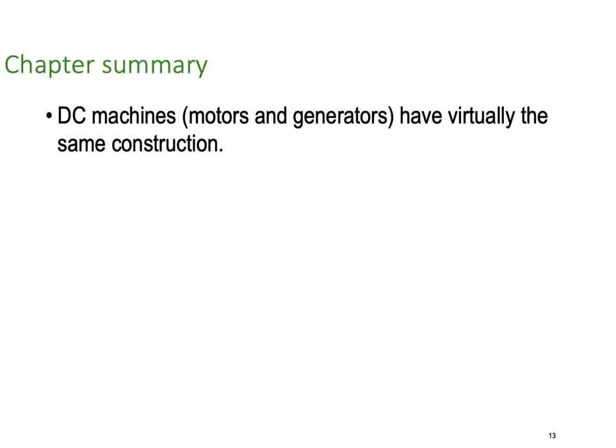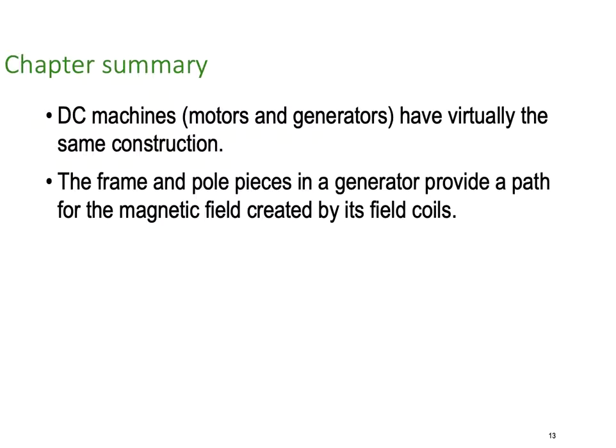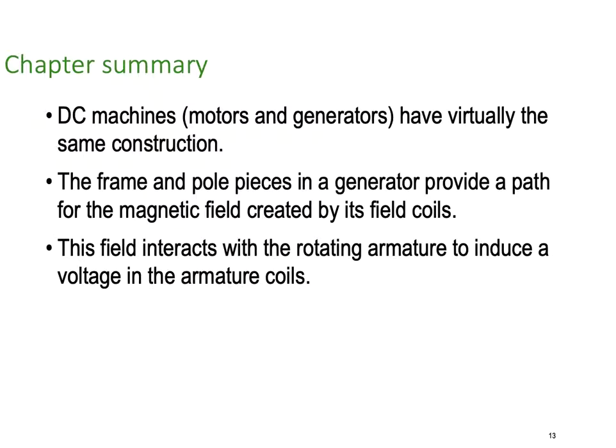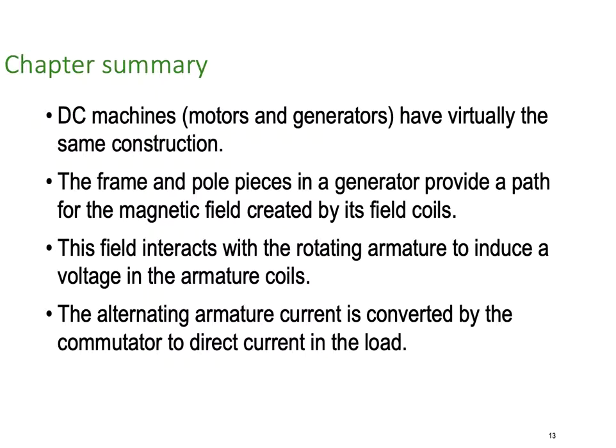Let's have a summary of the lesson. DC machines - motors or generators - have virtually the same construction. A generator can be a motor and a motor can be a generator in the DC world. The frame and pole pieces provide a path for the magnetic field created by the field coils. The field interacts with the rotating armature to induce a voltage in the armature coils. The field creates a flux and the armature cuts the flux. The alternating armature current is converted by the commutator back to direct current. The commutator is a switch that keeps the current flowing in the same direction all the time.